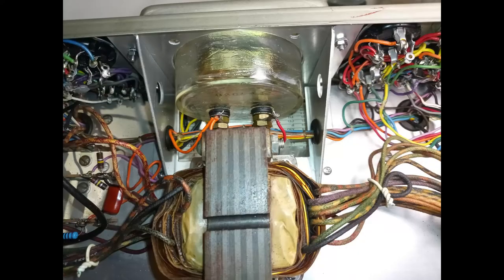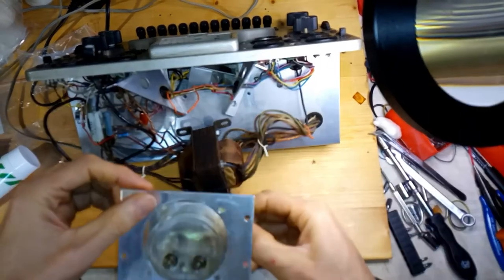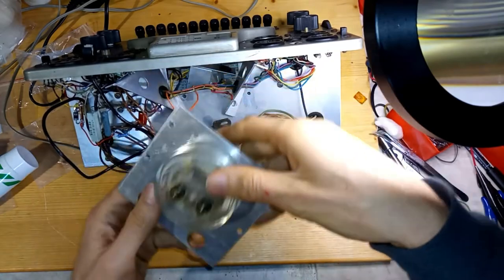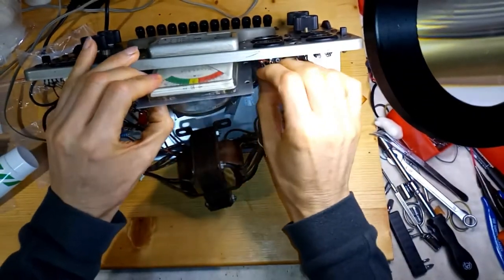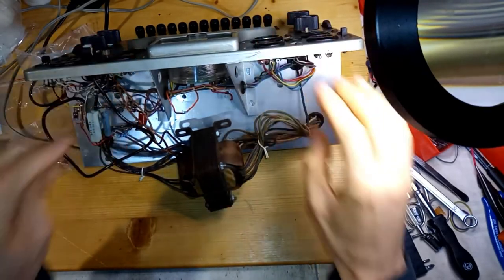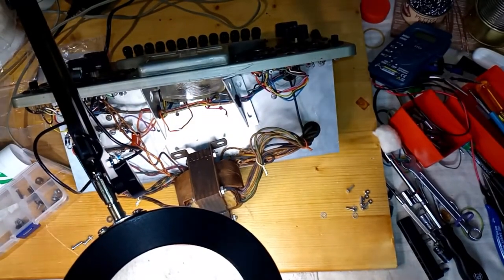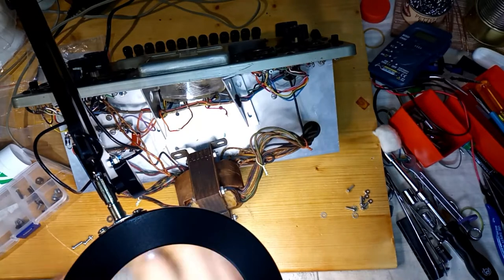However, this is not a straightforward procedure. Even though it is not recommended to remove the meter, these pictures have shown the necessary steps, in case anybody had to do the same for whatever reason. The following video clips, instead, show the reinstalling process. For the occasion, some stainless steel Phillips head screws are used, in place of the original ones.